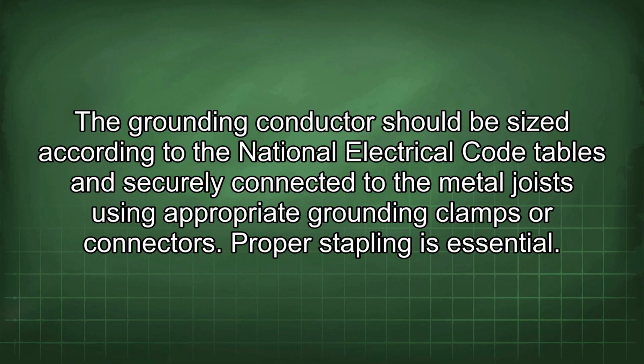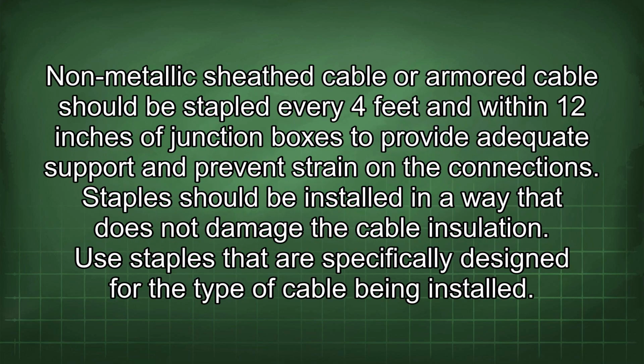Proper stapling is essential. Non-metallic sheath cable or armored cable should be stapled every 4 feet and within 12 inches of junction boxes to provide adequate support and prevent strain on the connections. Staples should be installed in a way that does not damage the cable insulation. Use staples that are specifically designed for the type of cable being installed.